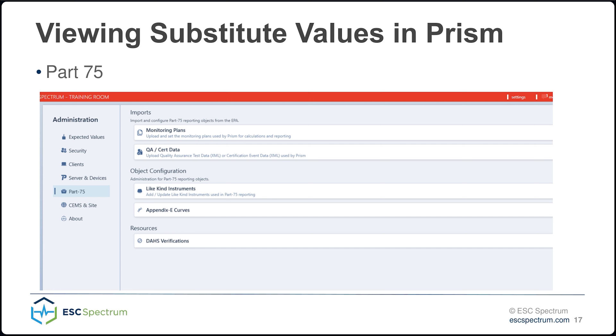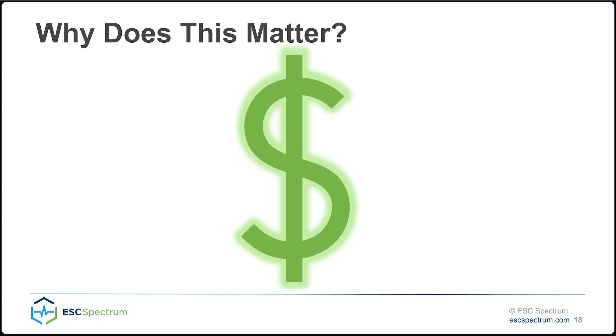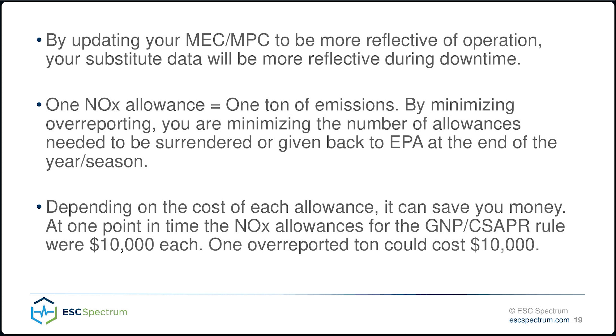Why does any of this matter? Money. You do not want to be over-reporting — nobody wants to do that — especially with all the changes going on with the good neighbor plan. By updating your MEC and MPC to be more reflective of operation, your substitute data will be more reflective during downtime. One NOx allowance equals one ton of emissions. By minimizing over-reporting, you're minimizing the number of allowances needed to be surrendered to the EPA at the end of the year season. At one point allowances were $10,000 each, so one over-reported ton could cost $10,000. This can be a good suggestion for accounting purposes simply.